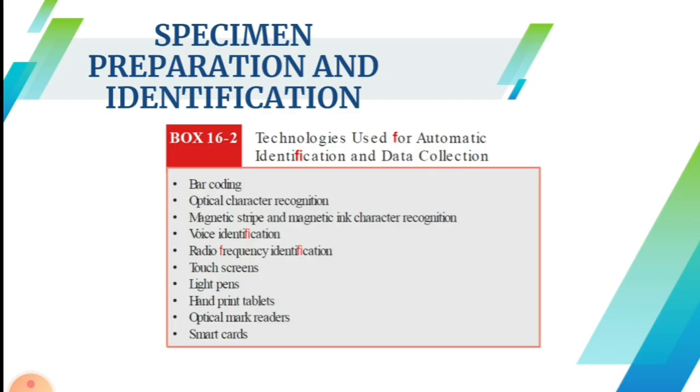This label contains patient demographics and also may include test requests. The barcode labeled tubes are then transferred to the loading zone of the analyzer, where the barcode is scanned and the information is stored in the computer's memory. The analyzer is then capable of monitoring all functions of identification, test orders and parameters, and sample position. Certain analyzers may take test requests downloaded from the laboratory information system, or the so-called LIS, and run them when the appropriate sample is identified and ready to be pipetted.